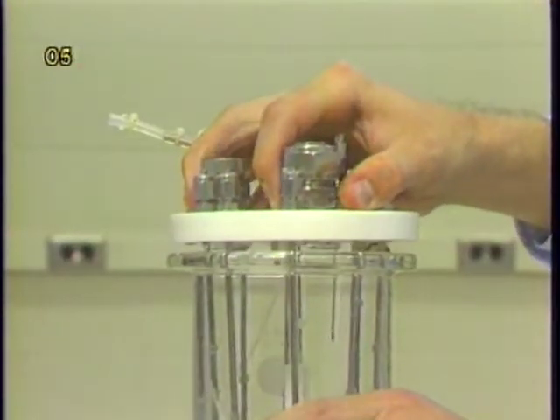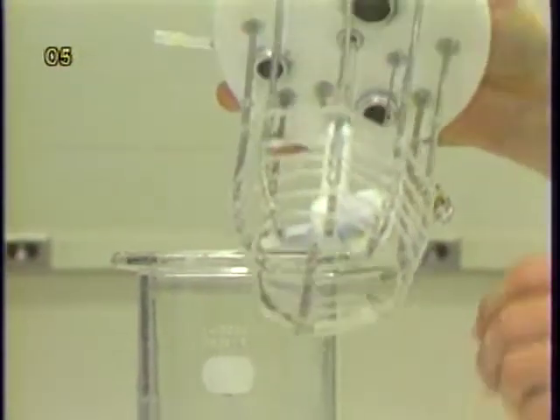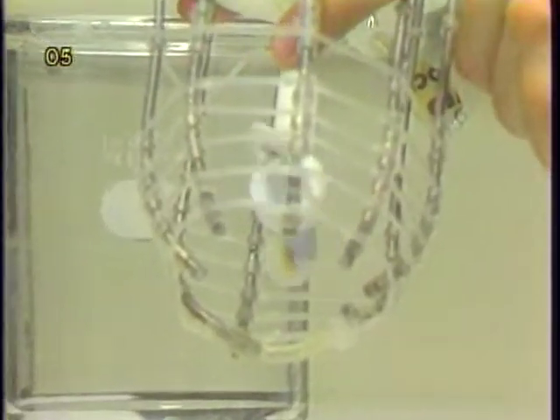With a marine impeller or pitched blades, the fluid can be pumped either upward or downward. Our observation with one to two liter vessels revealed no difference in cell growth whether the fluid was pumped either upward or downward. However, we feel that pumping the liquid upward is better.